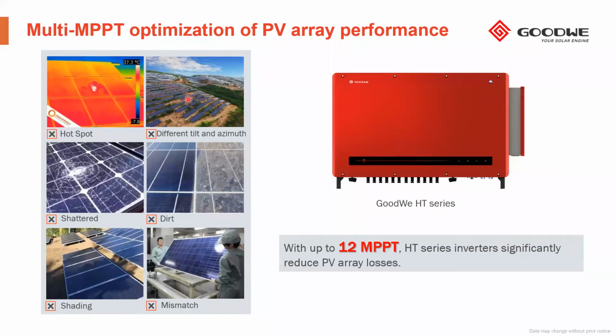Of course, it's mandatory here - I would say it would be required to use a multi-MPP tracker string inverter to optimize the PV array. Because if you use one MPP tracker inverter, like a central inverter, the inverter will work in a non-optimal way, and for sure the PV modules, along their life, will suffer from things like hotspots and other physical phenomena. That's not the topic of this presentation, but for sure, when we face different tilt and azimuth, we need to think from the design point of view about using a multi-MPP tracker inverter.